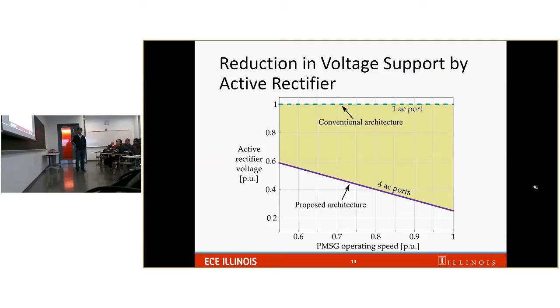So we see that the gain of this architecture, first of all, is that we need an active rectifier rated for at most about 60% of the DC bus voltage. So that is a 40% reduction in the switch rating. That is the first gain for this architecture.